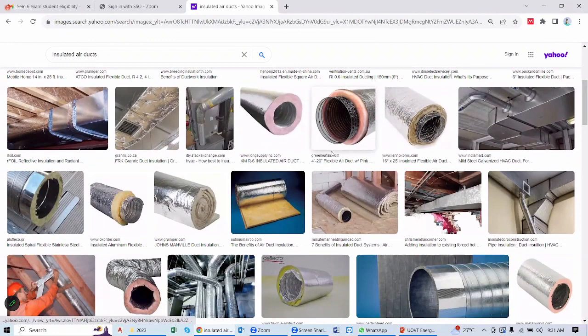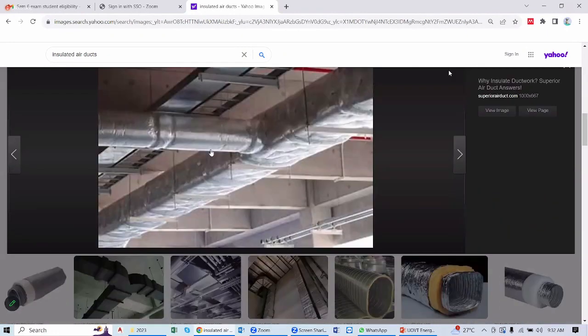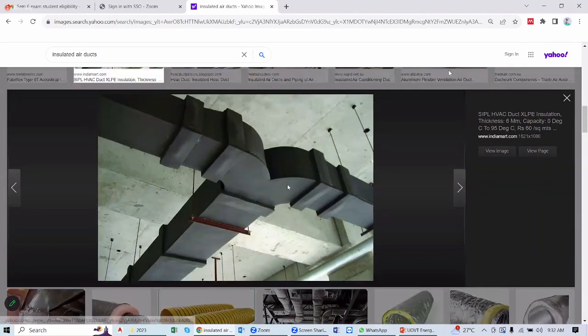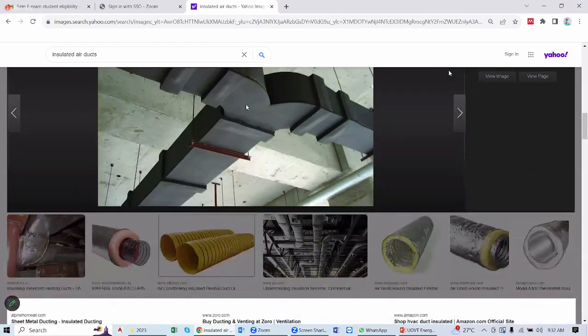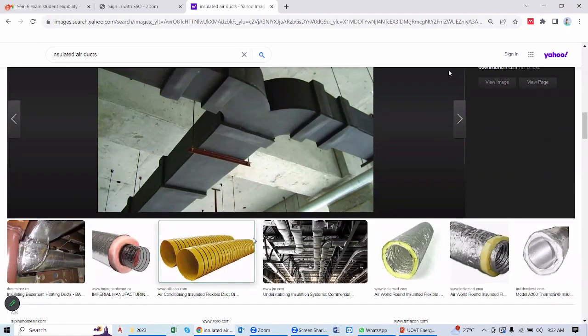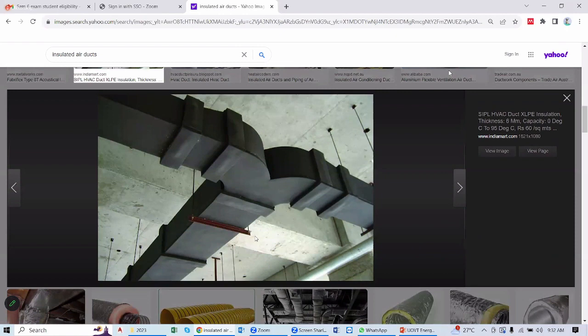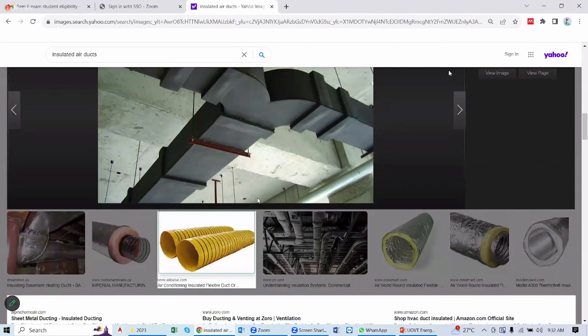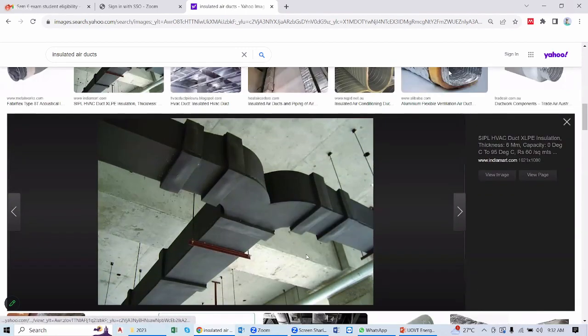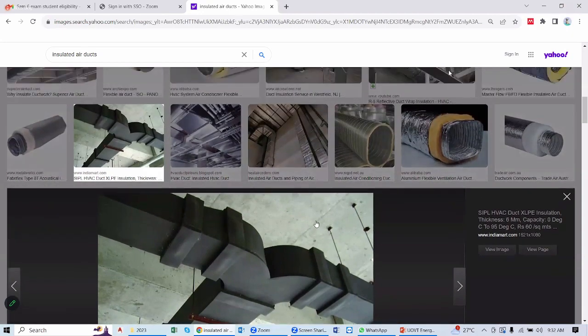yeah, so you have to insulate something like this, or you can use, what do you call it, Armaflex or Thermaflex. They are brand names which are used to insulate the ducts and to ensure that condensation doesn't happen if they are at a different temperature. So if it is inside the ceiling, then definitely it's at a different temperature. But if your ducts are actually exposed, you don't need to insulate, because they are at the same temperature as the air inside.